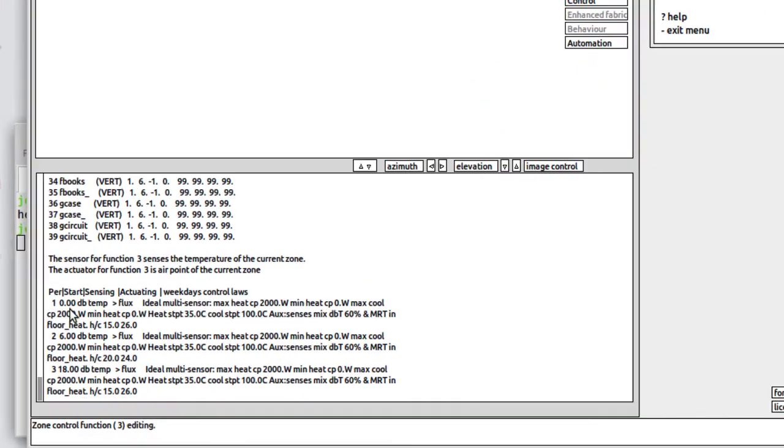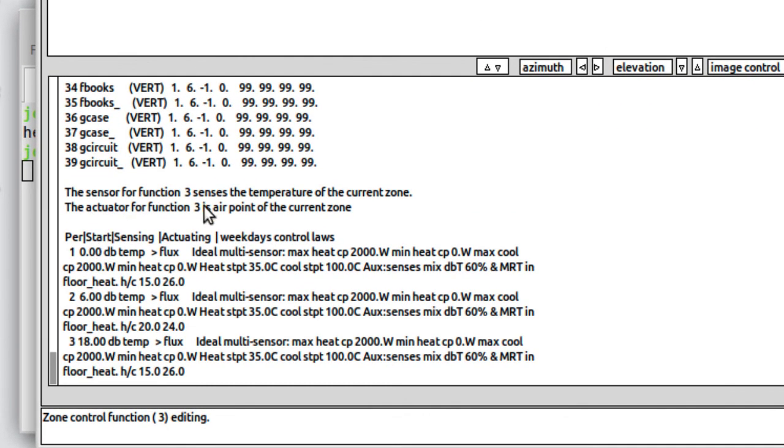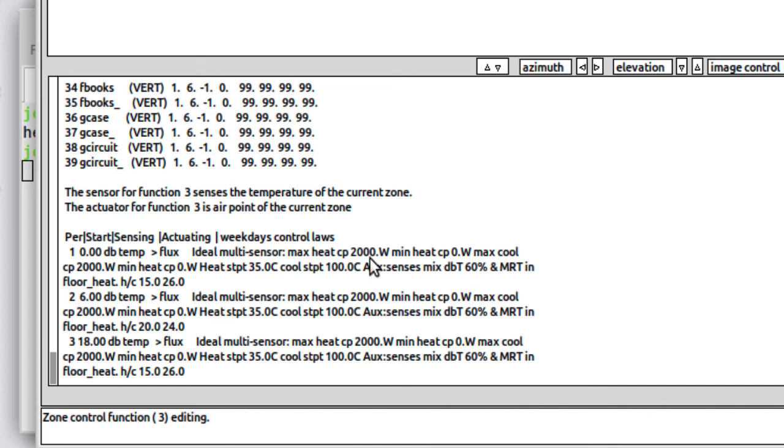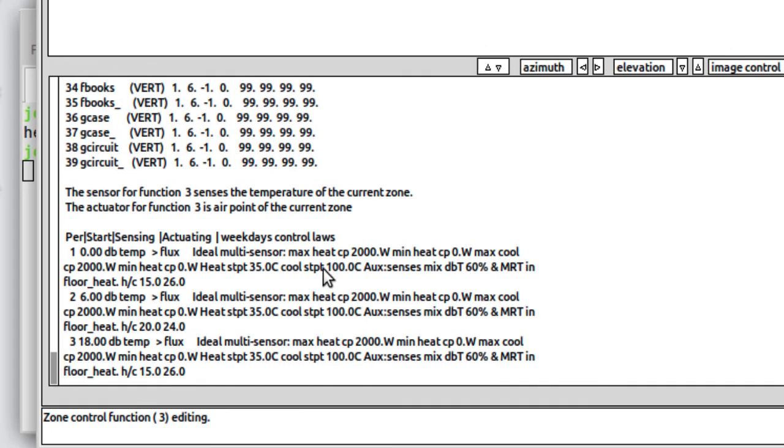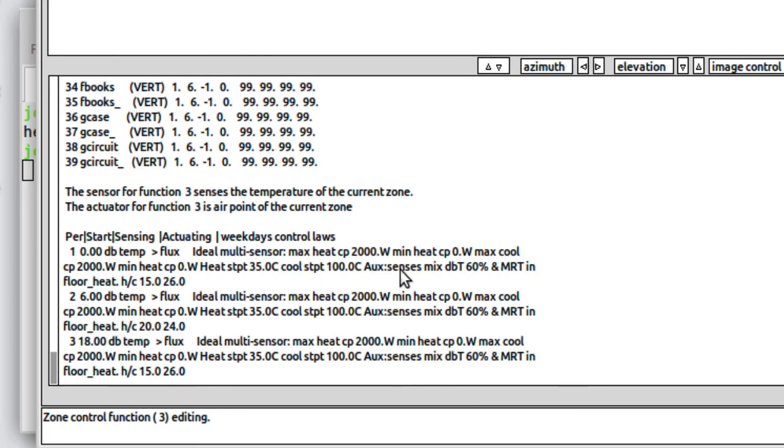If we open up that control, basically we've got an ideal multi-sensor control. A multi-sensor controller allows us to actuate in one zone based on what is sensed in another zone. So we're sensing the conditions in the room and we're doing the actuation within the thin floor zone. We've got a heat capacity of two kilowatts in that thin floor zone and a heating set point of 35 degrees within that thin zone. We set the cooling so it never comes on.